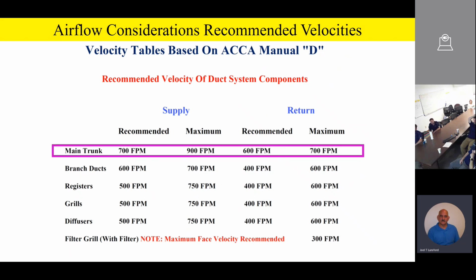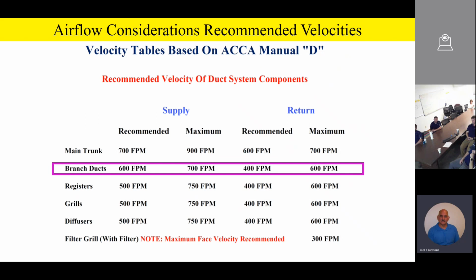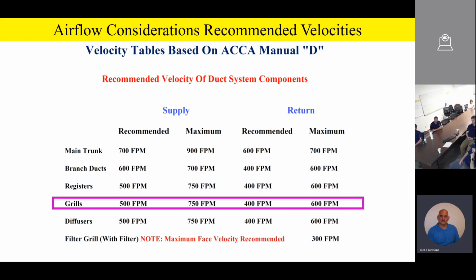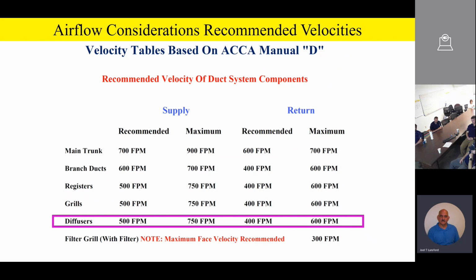And you can see there's Manual D, and we're not going to go over every little point in here, but we want to bring out some reminders for everybody that velocity is an important component of designing a duct system. For instance, the recommended velocity on the main trunk is 700 feet a minute, not to exceed 900. For your branch runs, 600 is recommended. Registers, grills, and diffusers, about 500 feet a minute is recommended, with a maximum of 750. You get the idea. So this velocity table is important when we design a duct system.